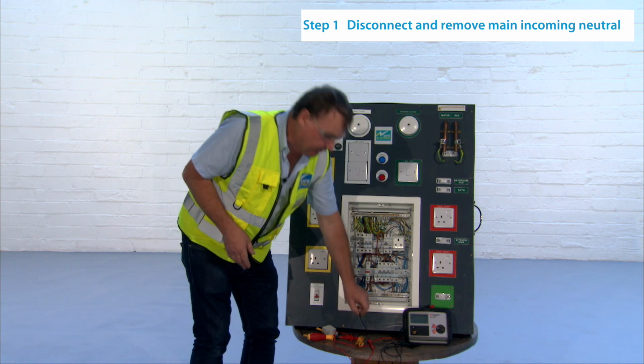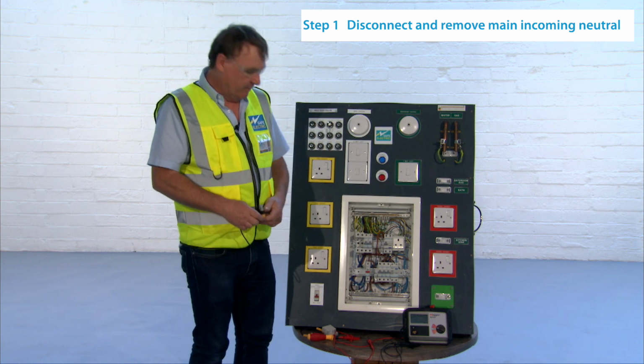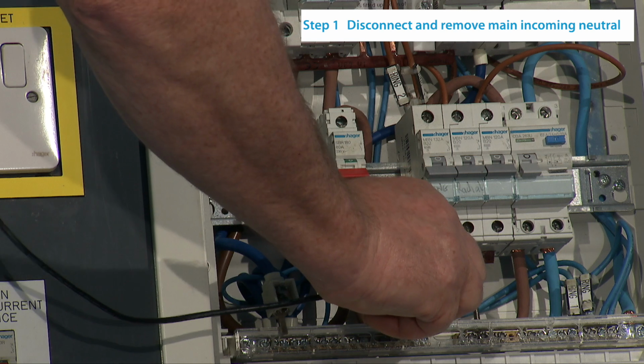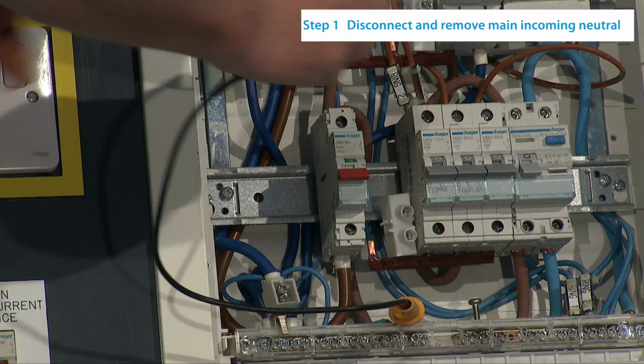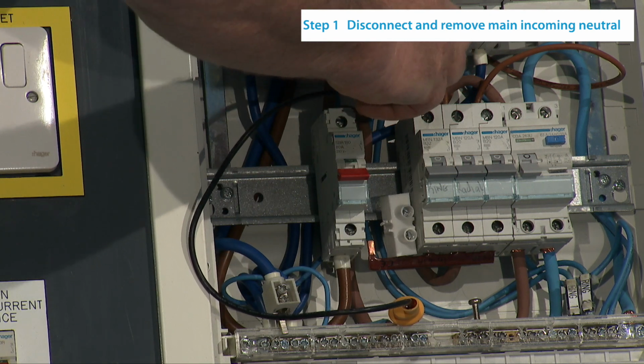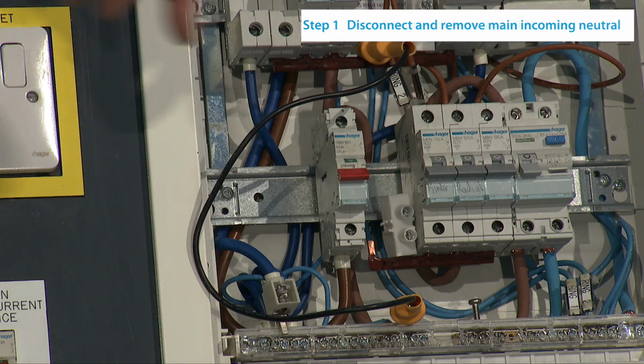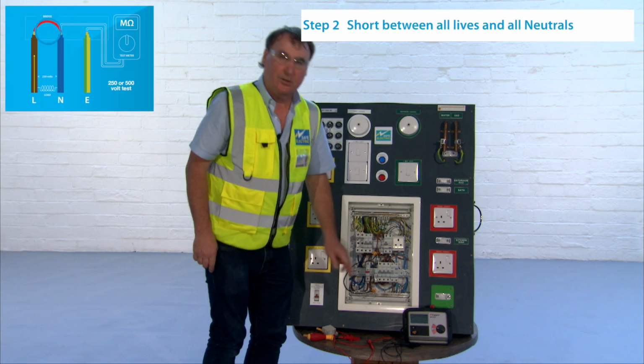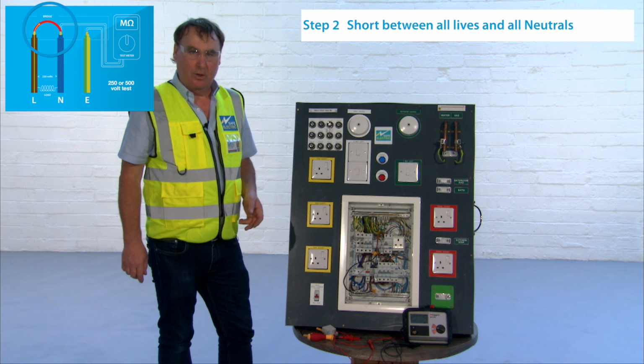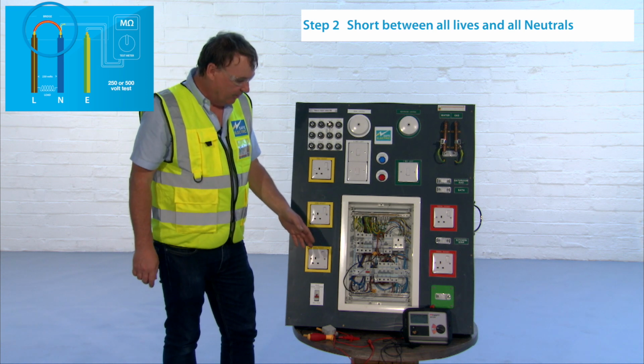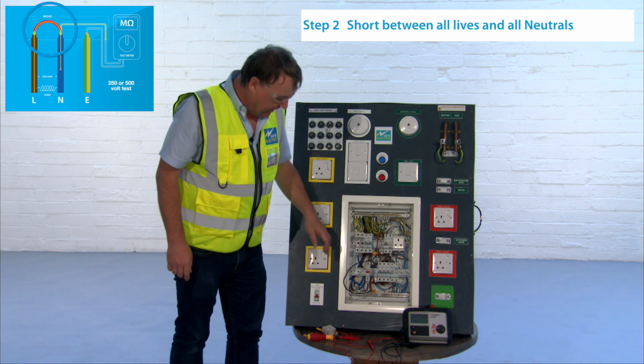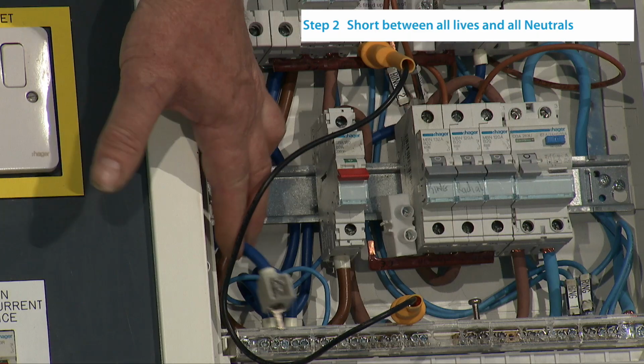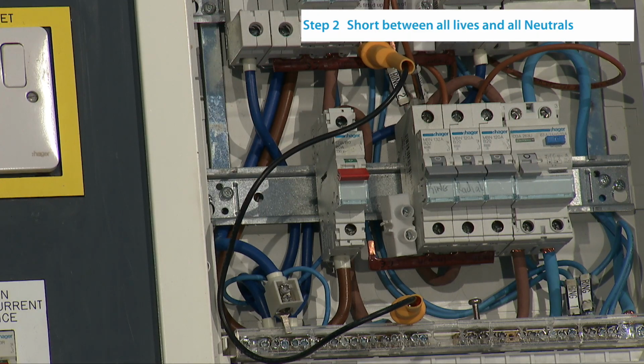Step number two is to create a short between the main neutral bar and the main live bar. And I'm going on to the lighting bus bar there. Remember, do not go on to the RCD neutral bar. It's the main neutral bar. A way that I remember it is, it's the same bar as you disconnected the main neutral from.